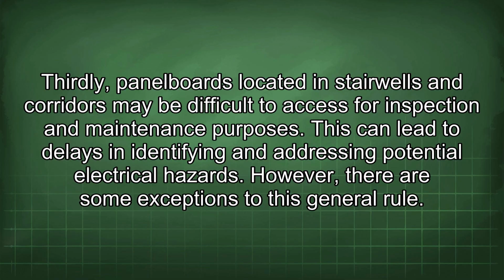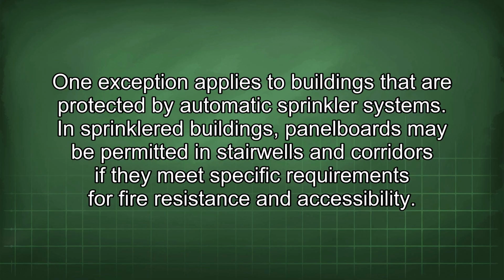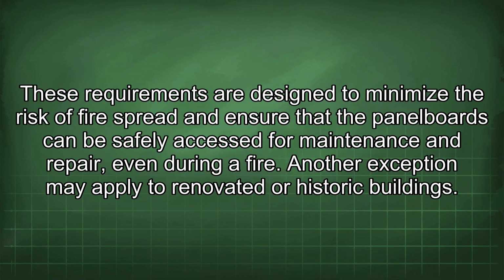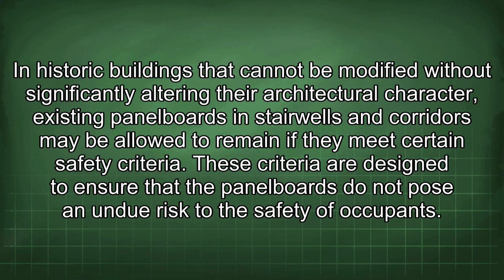However, there are some exceptions to this general rule. One exception applies to buildings that are protected by automatic sprinkler systems. In sprinklered buildings, panelboards may be permitted in stairwells and corridors if they meet specific requirements for fire resistance and accessibility. These requirements are designed to minimize the risk of fire spread and ensure that the panelboards can be safely accessed for maintenance and repair, even during a fire. Another exception may apply to renovated or historic buildings. In historic buildings that cannot be modified without significantly altering their architectural character, existing panelboards in stairwells and corridors may be allowed to remain if they meet certain safety criteria. These criteria are designed to ensure that the panelboards do not pose an undue risk to the safety of occupants.